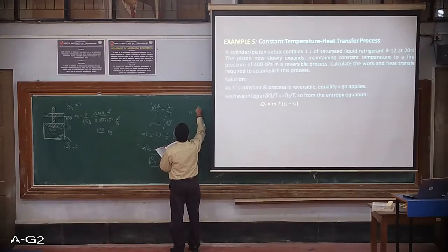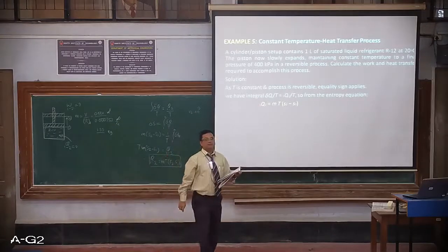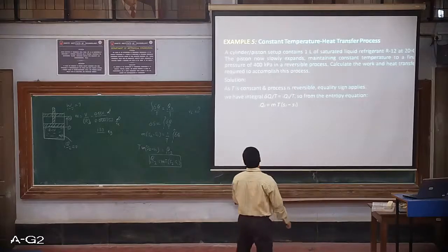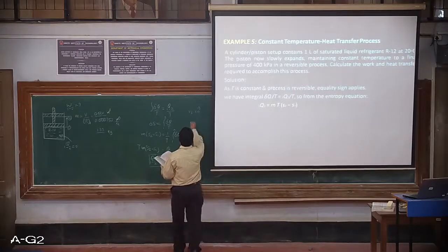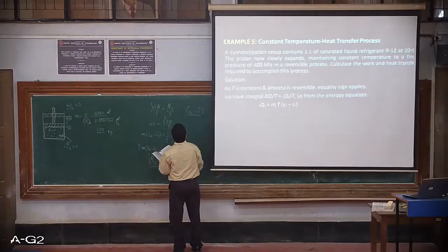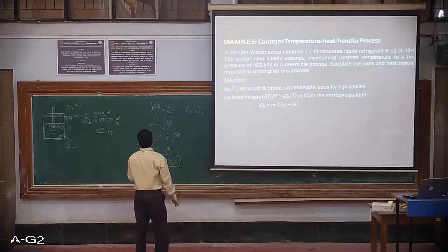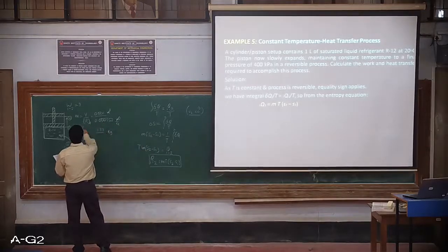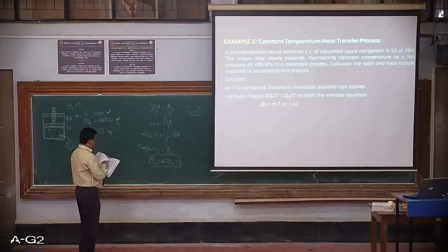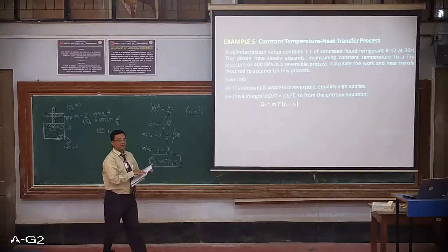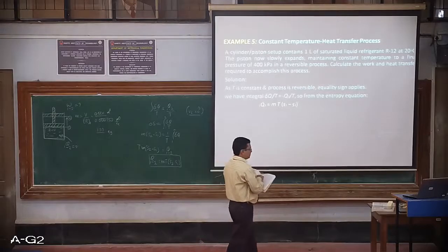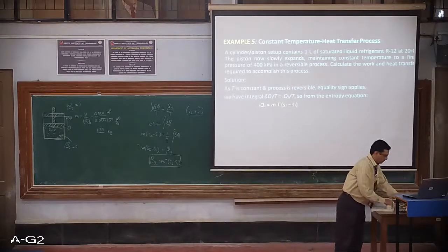Actually it should be into 10 to the power minus 3. So make a note of that. In all tables of refrigerant this misprint is given, so we can convert that value. For a given temperature of 20, for R12 the value is 0.752, and it should actually be divided by 1000, so it comes to 0.000752. That one change you must observe.